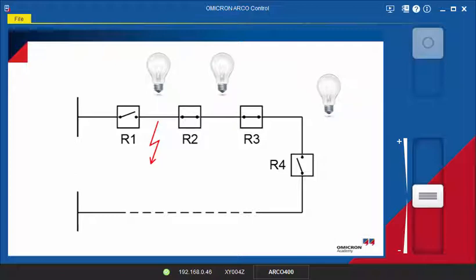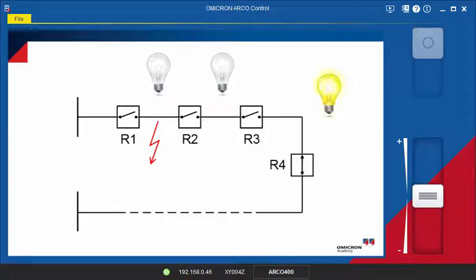R2 and R3 trip one after another to isolate the line segments due to the loss of voltage on both sides. The tie recloser R4 detects a loss of voltage on one side and closes after its configured close time so that the power supply for customers between R3 and R4 can be restored.